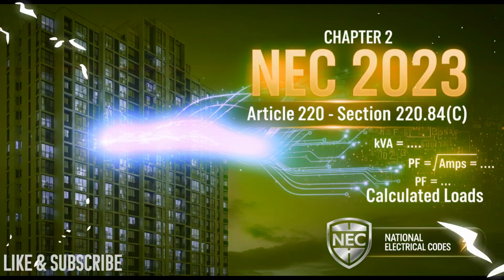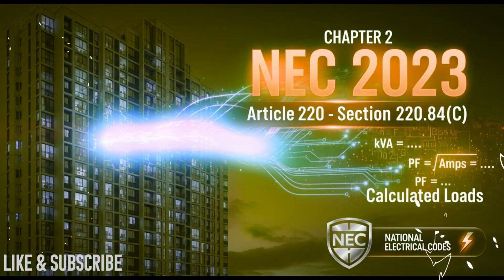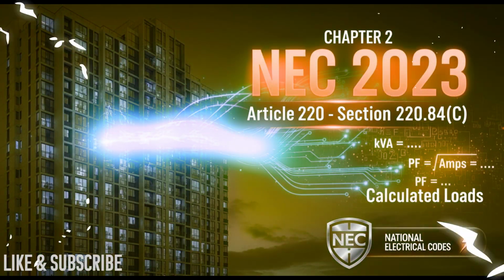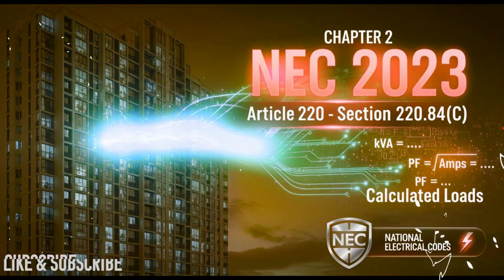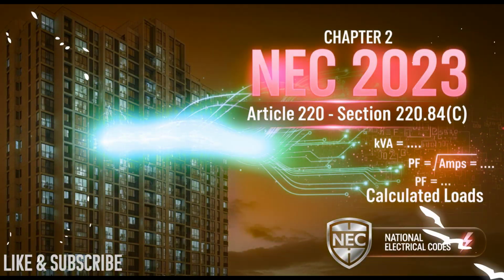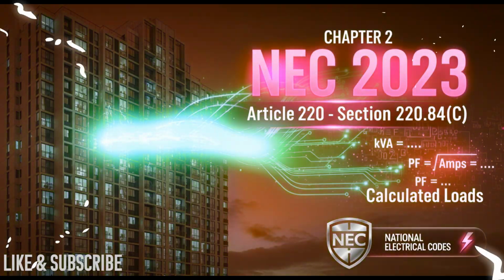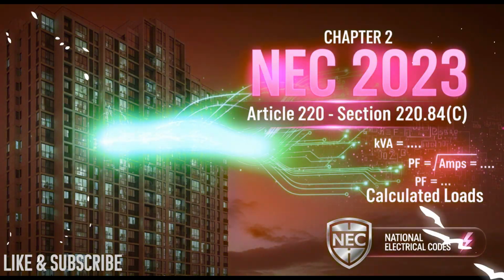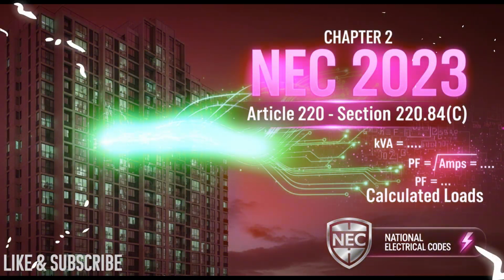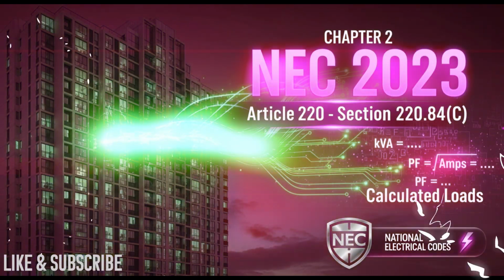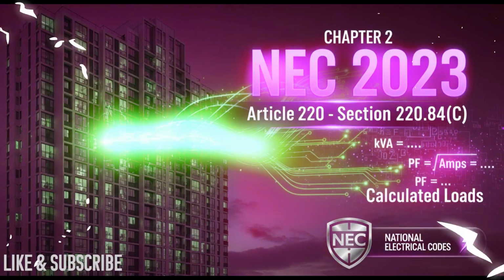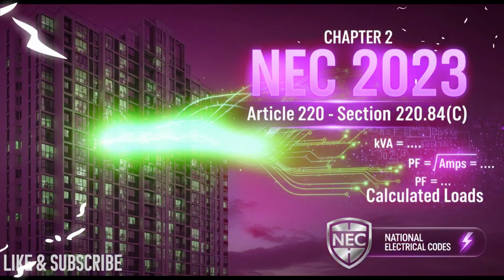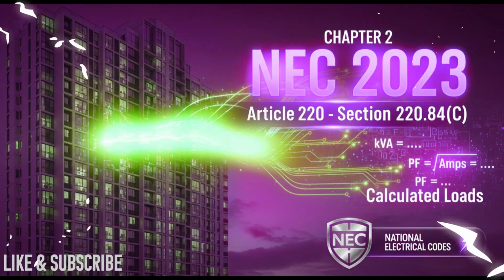You need to add up the nameplate ampere or kVA rating of all permanently connected motors that weren't already captured in that fixed appliance group, input 3. So think about common area equipment. Exactly. Pumps for maybe landscaping irrigation or a fountain, fan motors for ventilating hallways, or maybe the big motor for the shared parking garage door. Right, stuff that serves the whole building, not just one unit.